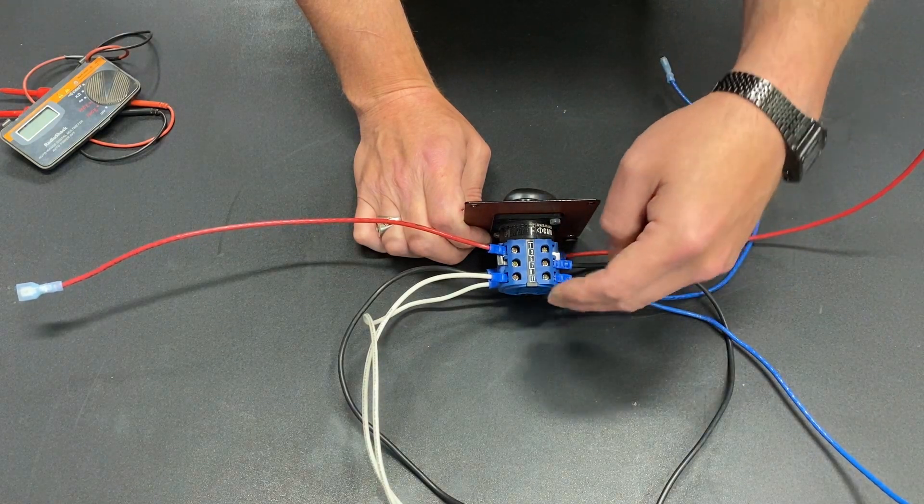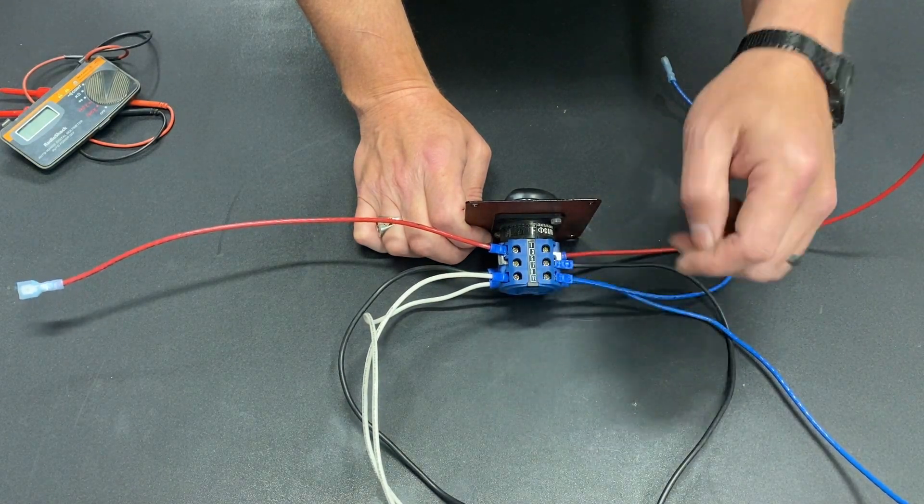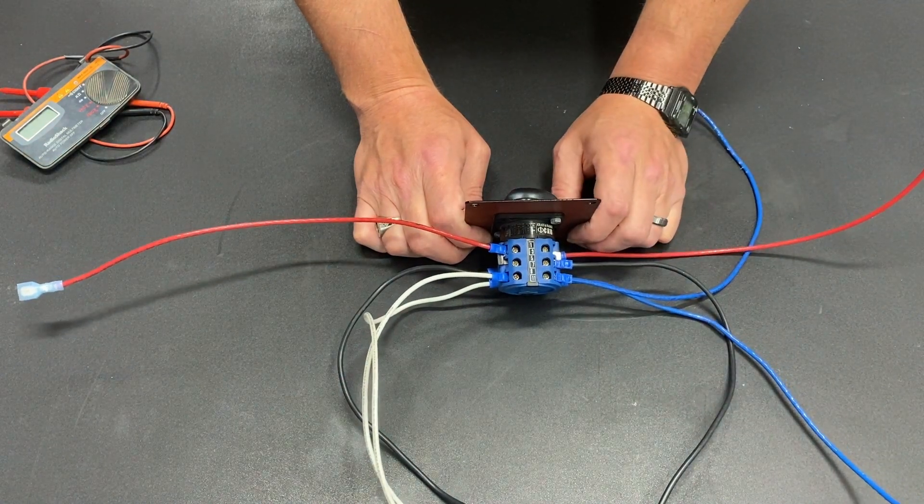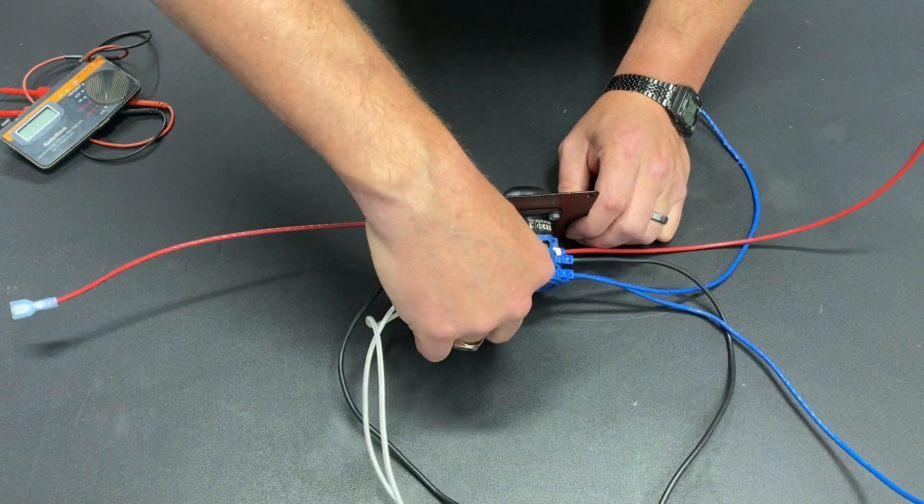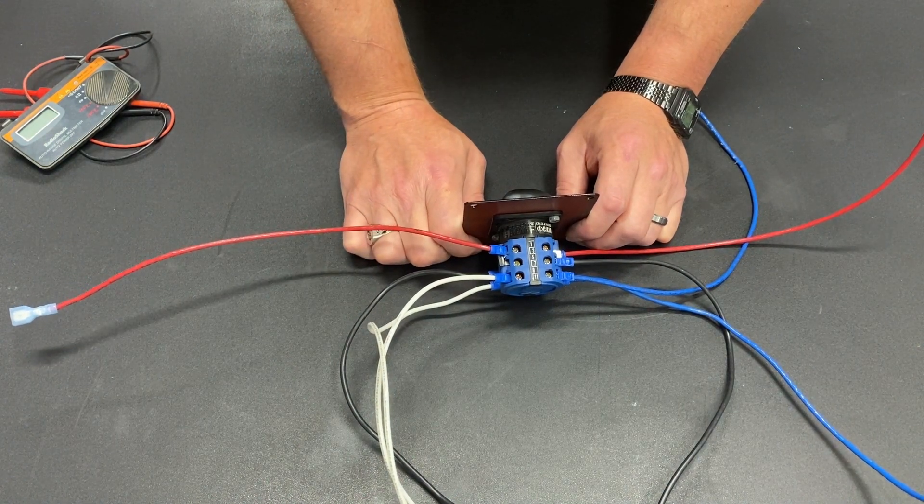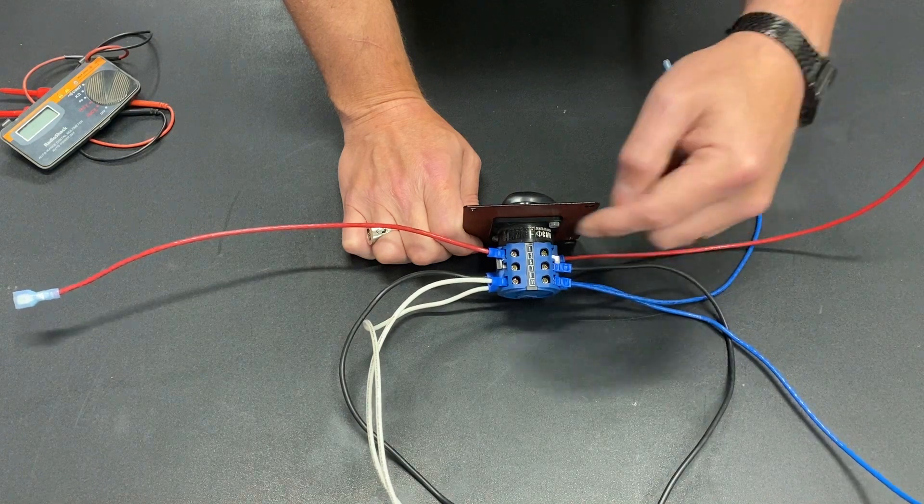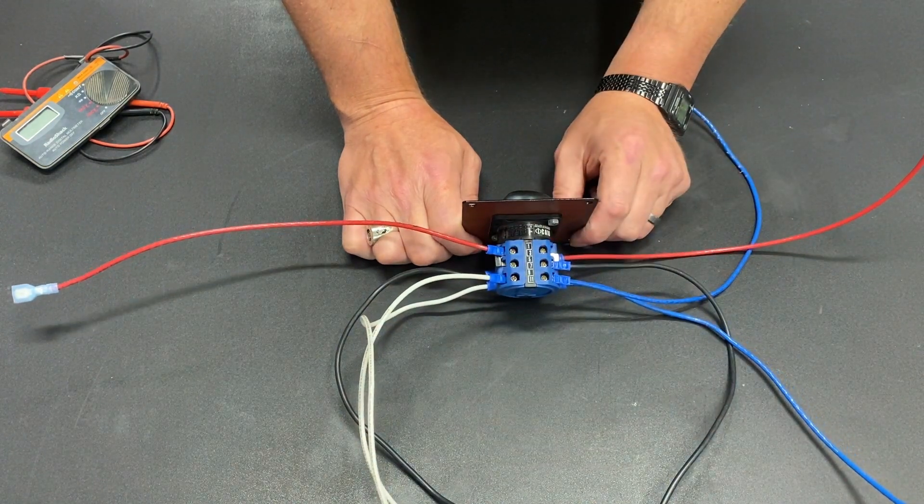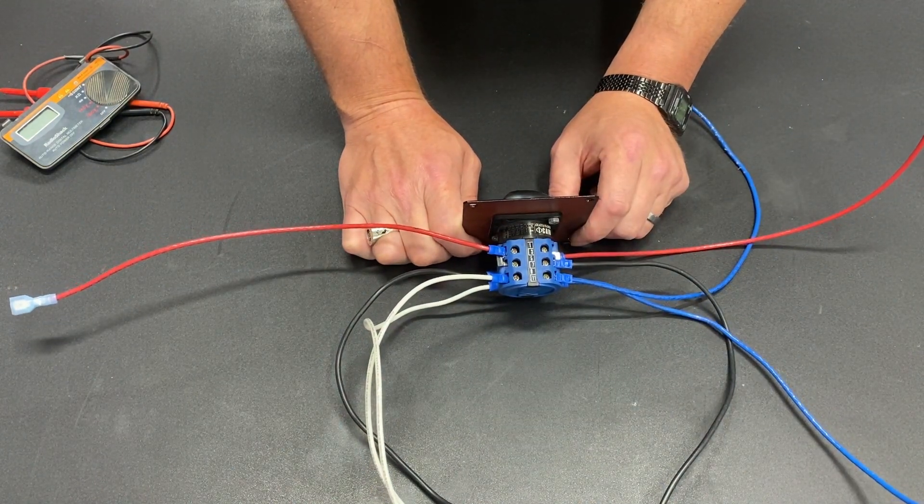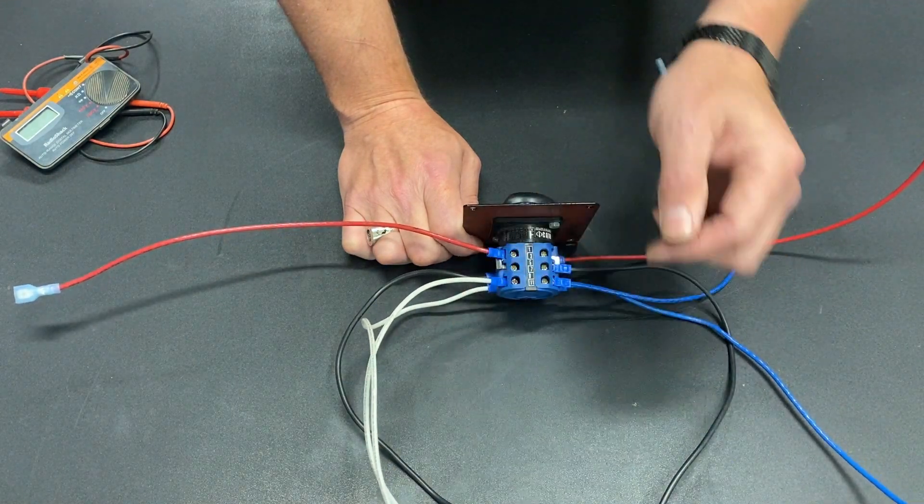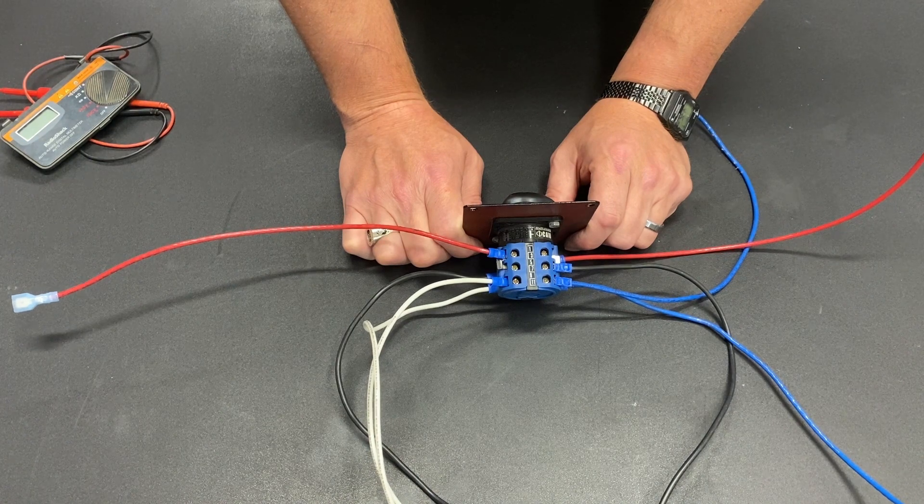And then these last four, the blue ones are going to go to my AC hot and my white ones are going to go to my AC neutral so that we're killing the power from here to here and from here to here when it's in the neutral position. But when it's in the forward position or the reverse position these wires are connected and supplying power to the relay.